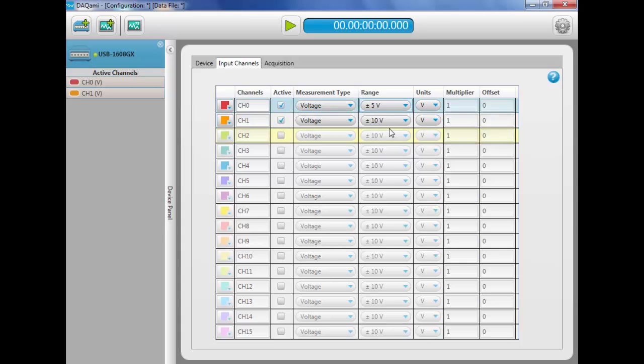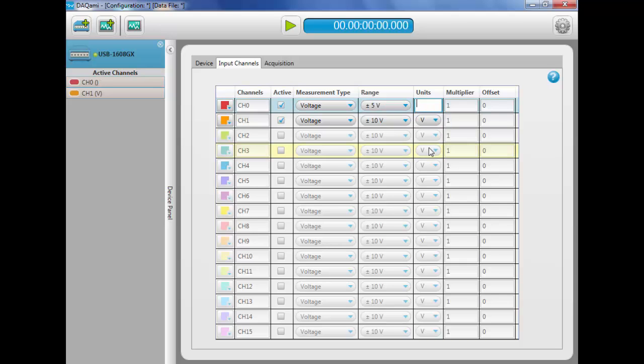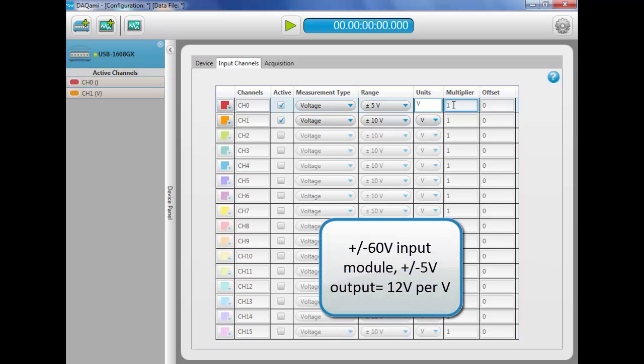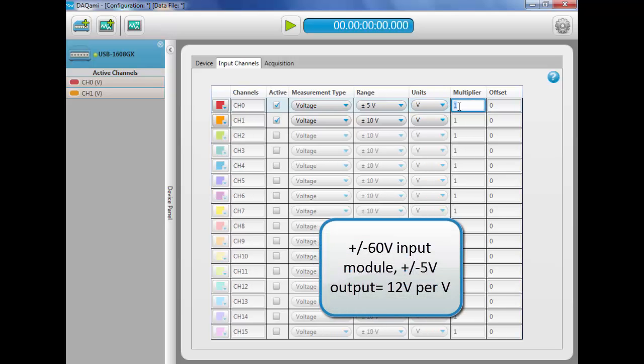We'll enter our units and add a value multiplier. For channel 0, we have a plus or minus 60-volt analog input module with a plus or minus 5-volt output, or a ratio of 12 volts per volt. So we'll enter a multiplier of 12.